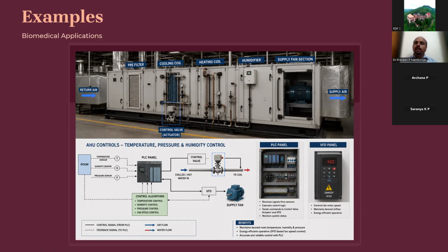Pressure I already said. I will control the air damper through actuation only. That actuator will work based on the system. Now humidity. How will I control the humidity? We told about the parameters, right? Temperature, pressure, you might have understood. So how can we control the humidity? We control the cooling coil and heating coil in a percentage to control the humidity. Both the cooling coil and heating coil will be operated to control the humidity of the room.